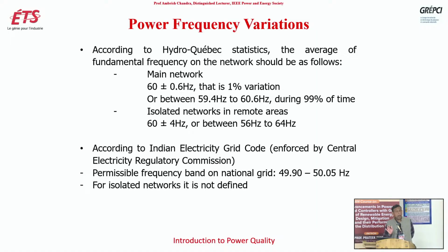Okay, so Hydro-Quebec is the utility company for the province of Quebec, and according to Hydro-Quebec statistics, the average of fundamental frequency on the network should be as follows. Main network, 60 plus minus 0.6 Hertz, that is 1% variation. Or between 59.4 Hertz to 60.6 Hertz during 99% of the time. So this is their standard.